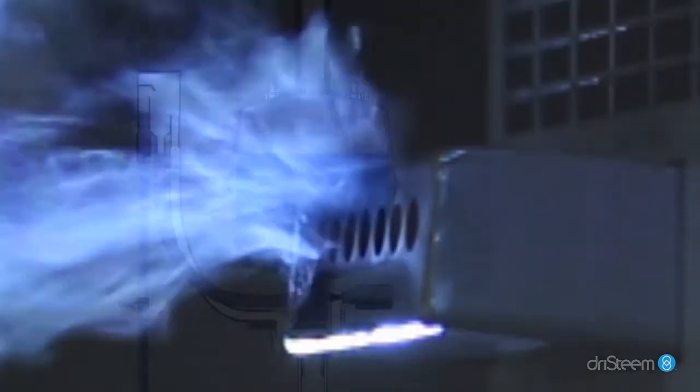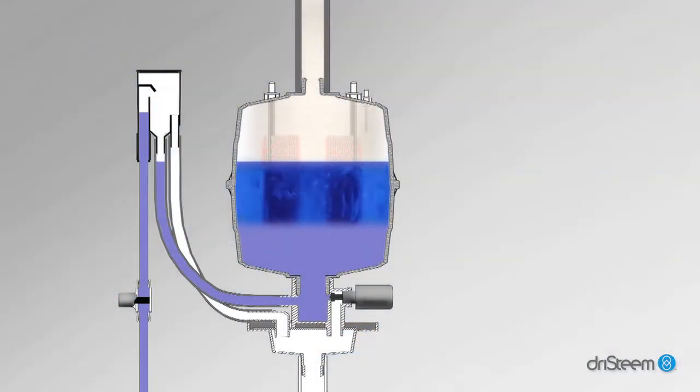As the water boils away, the amount of water covering the electrodes decreases and current flow decreases. When current flow decreases to a minimum level set by the controller, the fill valve opens to increase the water level, which increases current flow and in turn steam production.